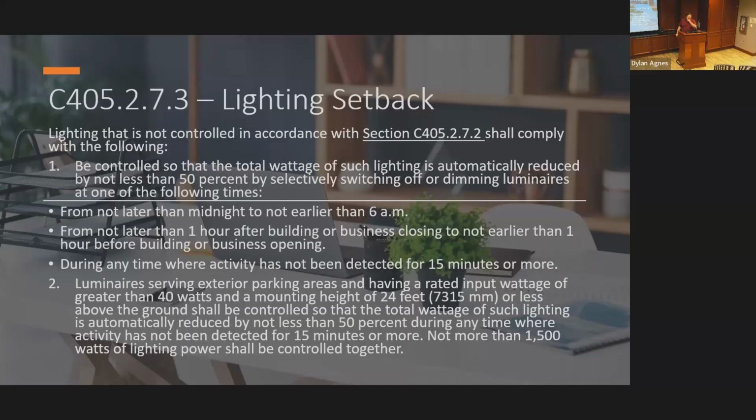But you're talking about reduced by not less than, so that means not full off, but to 50%. Yes, so you can go to 0, which I do not recommend, even for the case of energy efficiency. But we're going to say 50 here. For occupant comfort, I would do right at the line, 50%. I would not mess with that one.